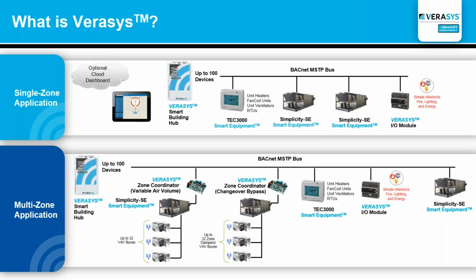The number one thing I tell contractors is that if you could follow the communication path, understanding your riser diagram, and follow the addressing needed based on our documentation, that is the most difficult part about installing a Verasys project. After that's completed, when you power everything up, everything will come into the system and start operating. At that point, you'll make simple configuration changes like adding descriptions, changing set points, adding schedules, and in the case of VAV, you'd have to put in your balancing information, which is no different than any other system in the world.